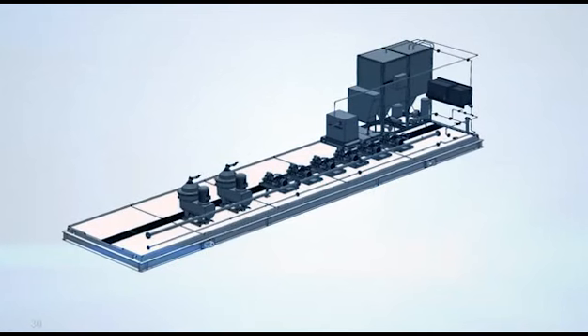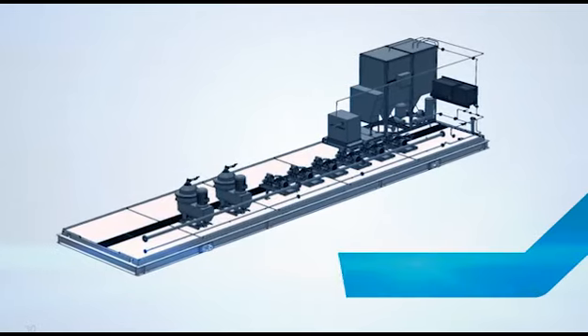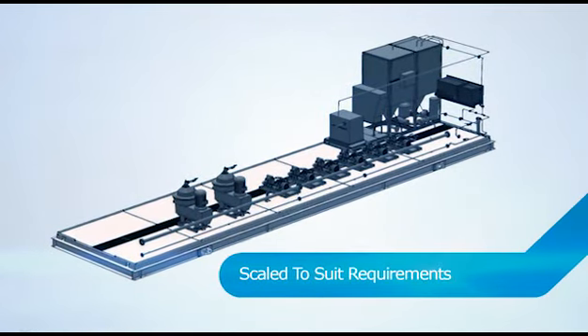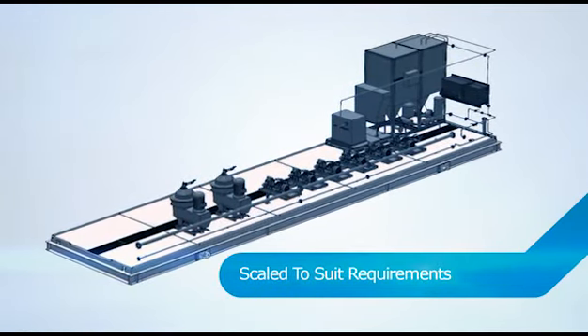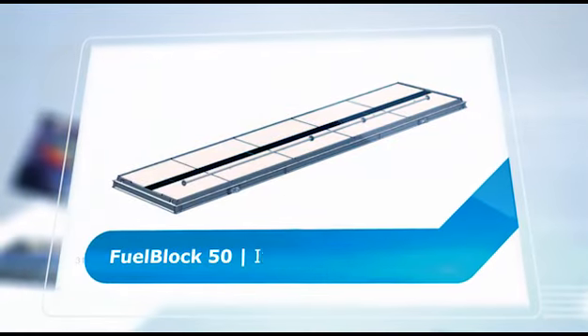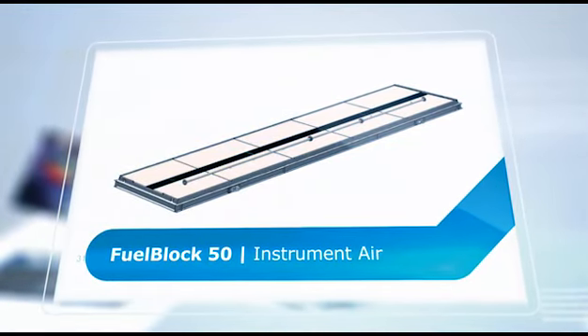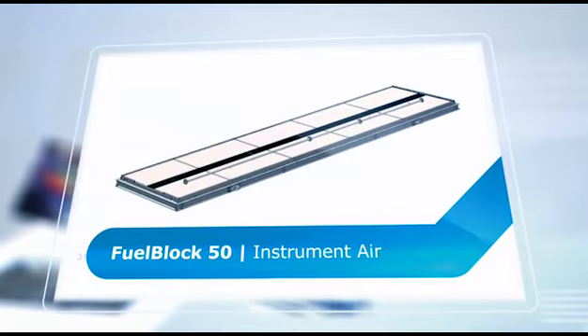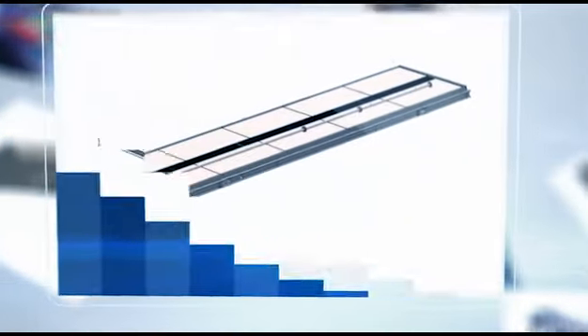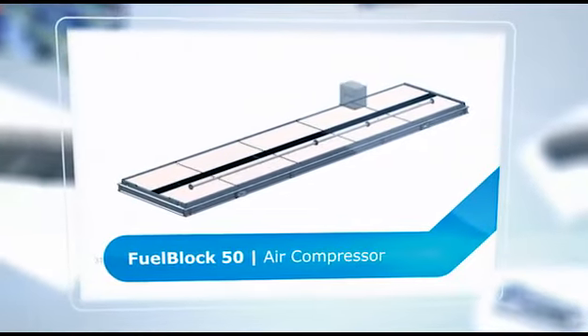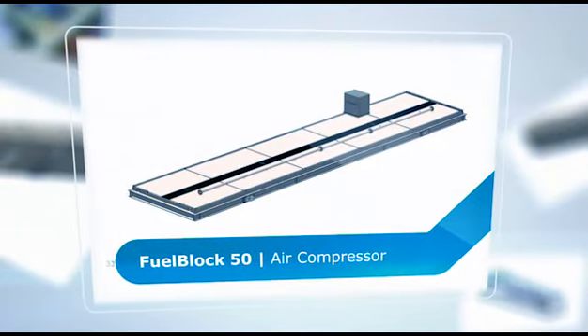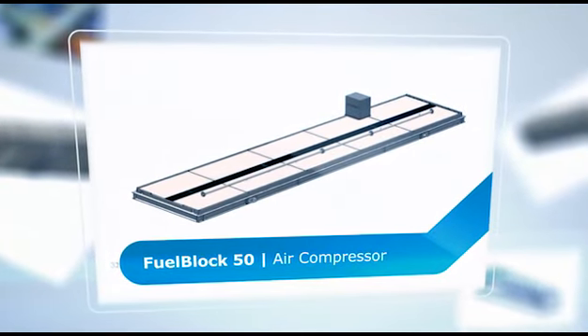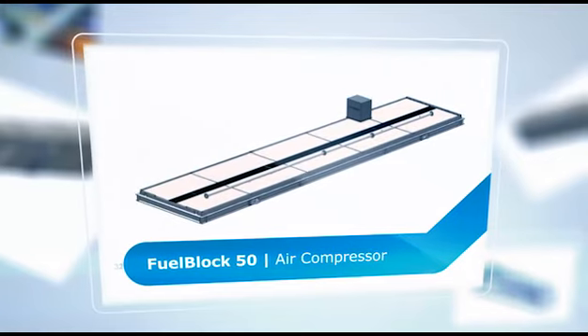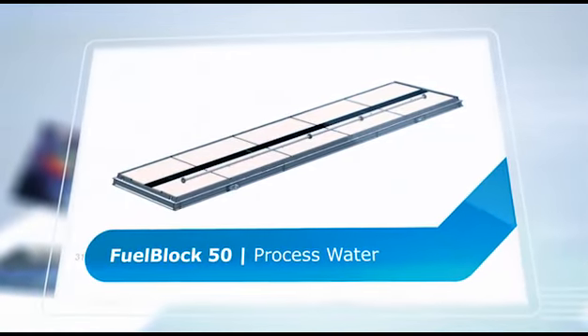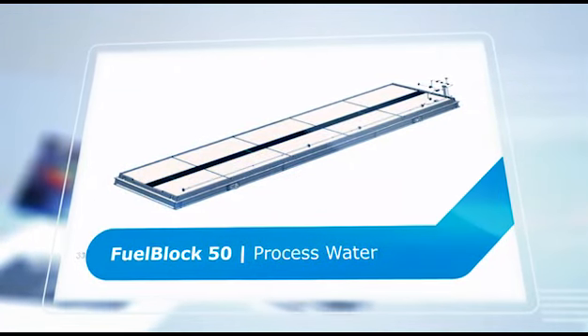The auxiliary and waste systems are modular in design and can be scaled to suit the specific requirements of each site. An oversized instrument air header provides additional storage capacity in the event of a disrupted supply. A self-contained screw-type compressor with integral refrigerant dryer can be provided for maintenance activities or at sites without a dedicated instrument air system. Process water is used for centrifuge bowl operations and fuel washing.